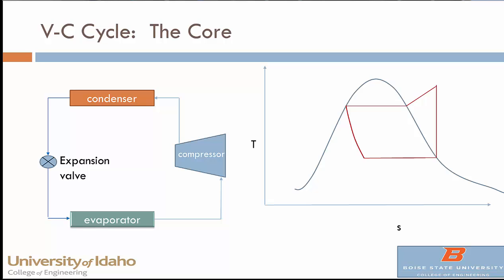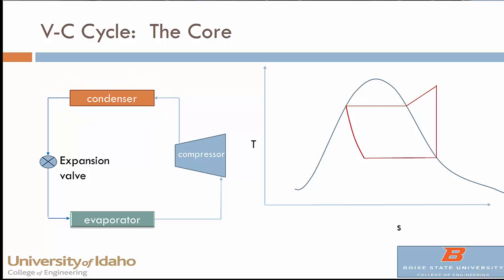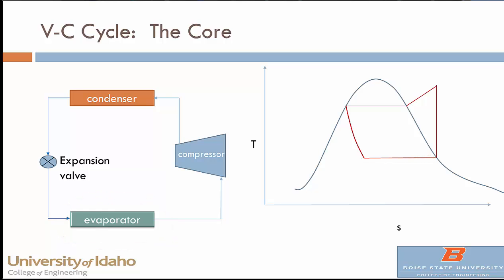The core of these systems is the vapor compression cycle. There are four main components. The compressor takes the refrigerant in the vapor phase to very high pressure and hence high temperature, sending it to the condenser where heat is rejected and the vapor condenses to a liquid. When you expand the liquid through a throttling valve, it gets very cold and exits as a mixture within the saturation region. That goes through the evaporator, where it absorbs heat at very low temperature and evaporates back into a vapor phase to go through the cycle again.